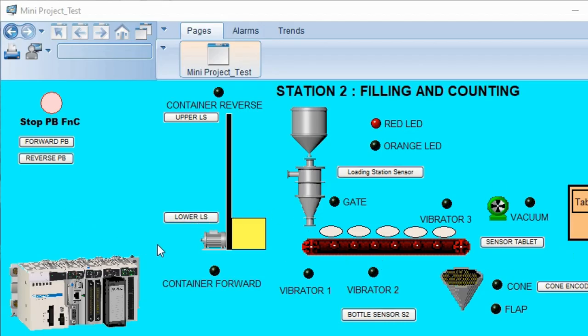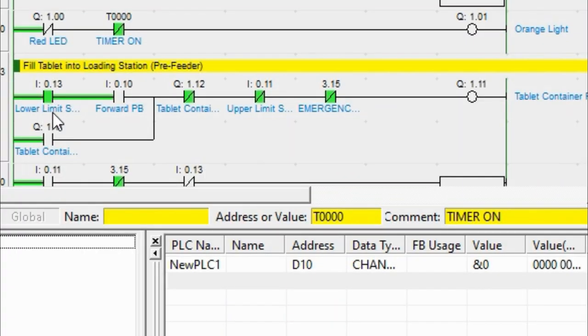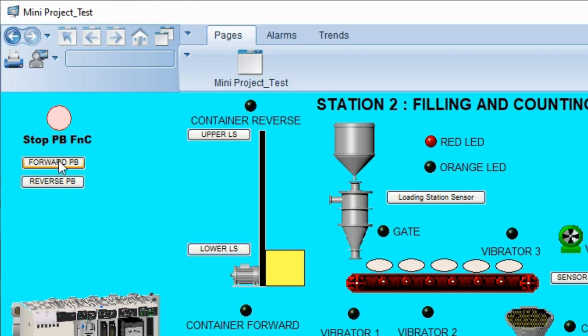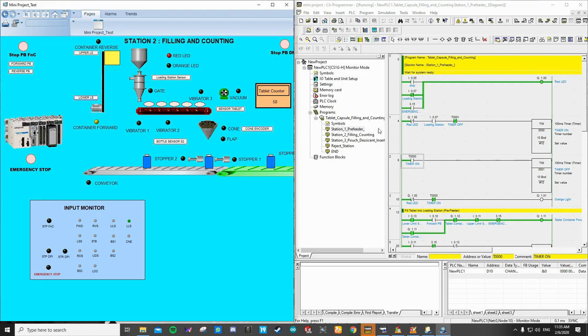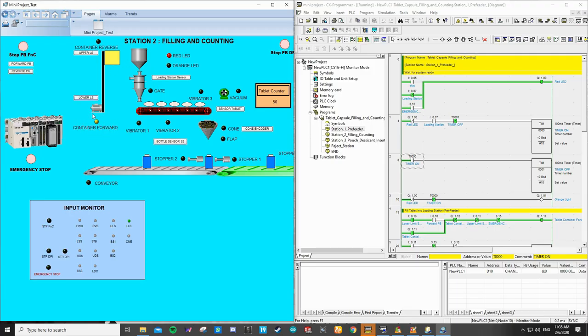For the simulation, first the box on the Pre-Feeder will contact the lower limit switch. As you can see here in the CX-Programmer, the input at address 0.13 will be on. This means the Pre-Feeder container has contacted the lower limit switch. After the condition is met, we press the forward push button to make the container move forward. As you can see, the CX-Programmer LED for output address 1.11 will be on.